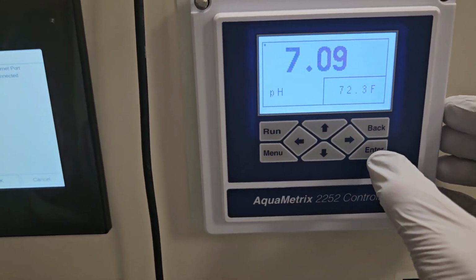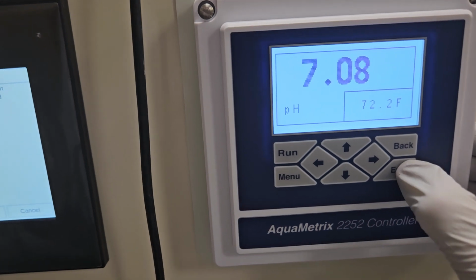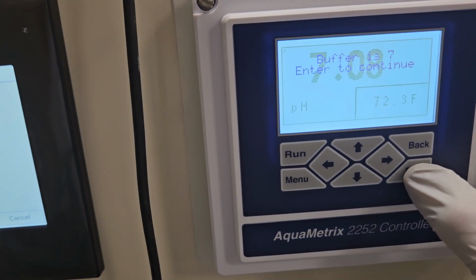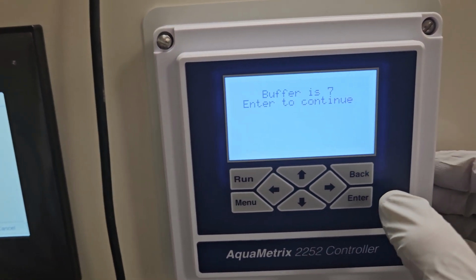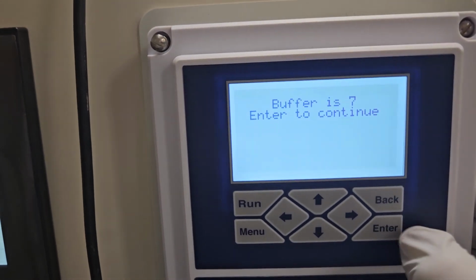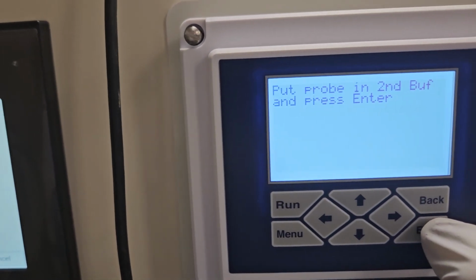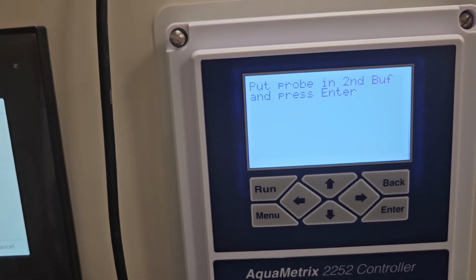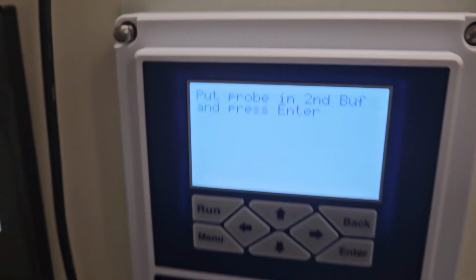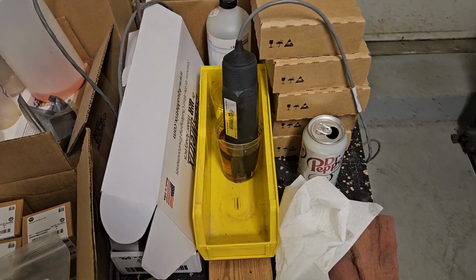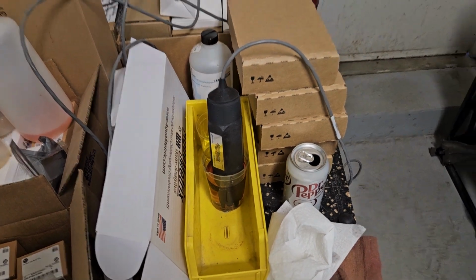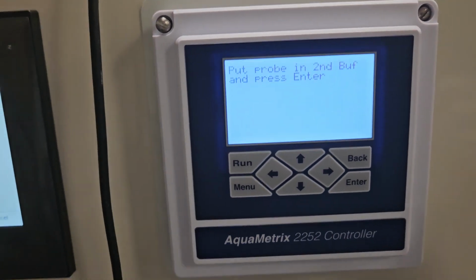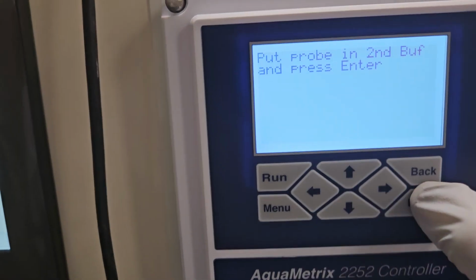Once it's stabilized, you can push enter again. It asks, is the buffer a 7 that it's in? You can push enter to continue. I'm going to push enter because it is in 7. Now it tells me to put the probe in the second buffer solution, which I'll do next. Okay, now the probe is placed back in pH 4. I can push enter to continue.